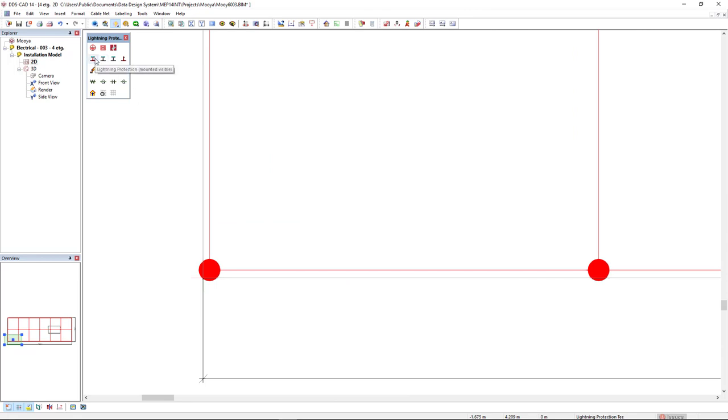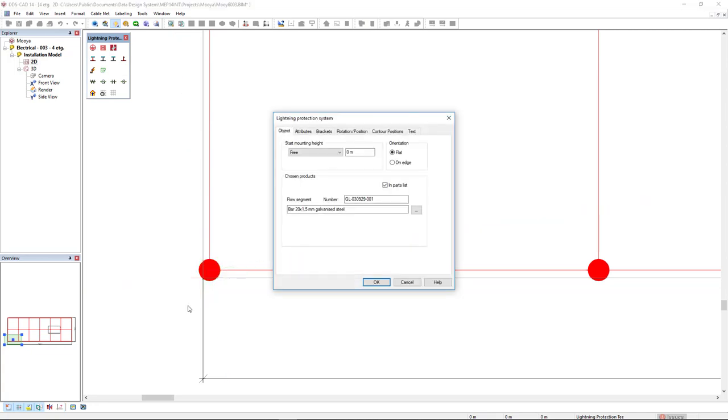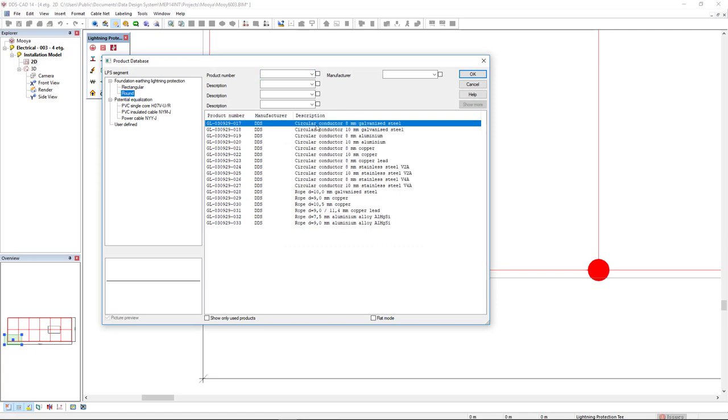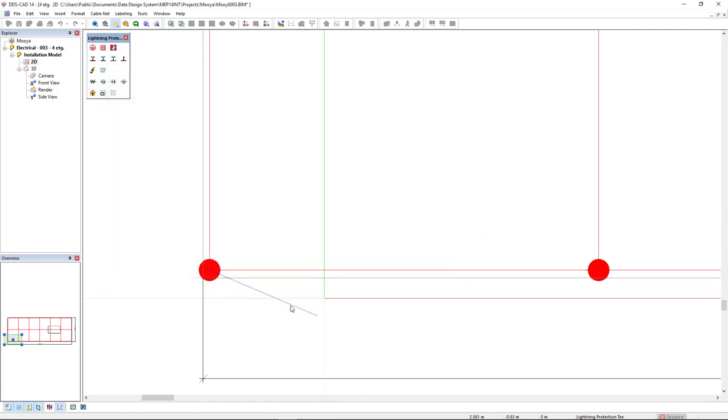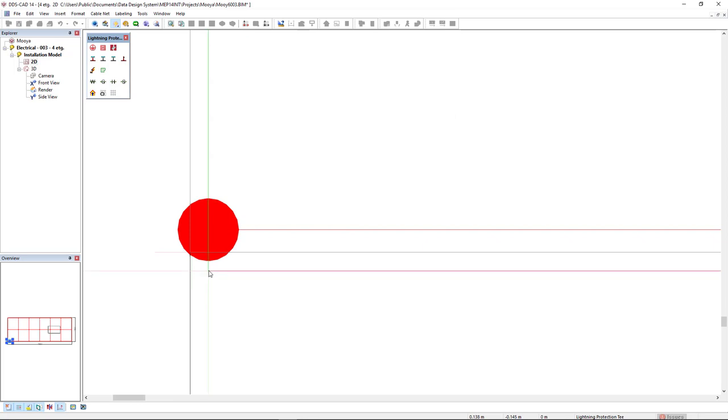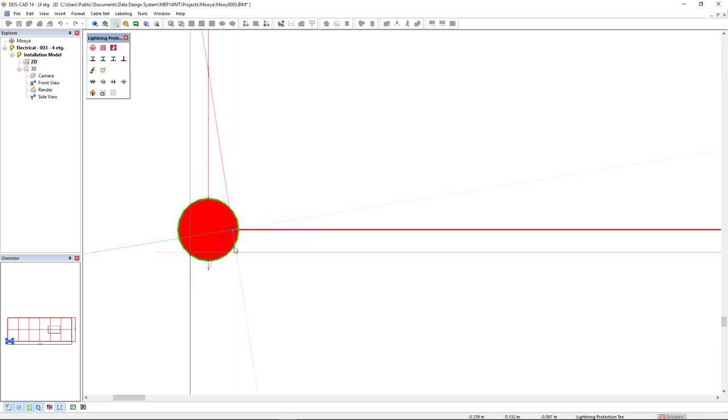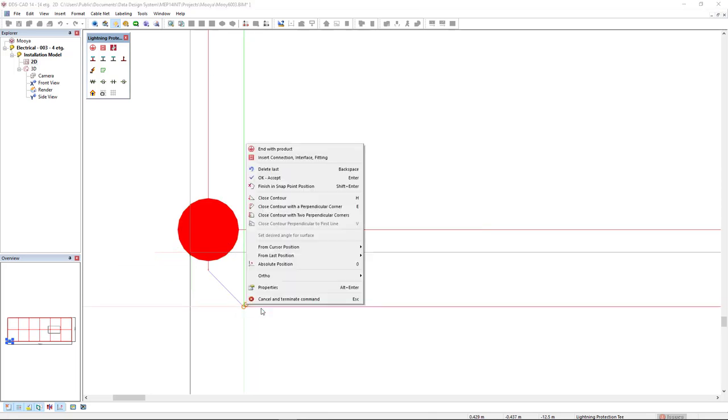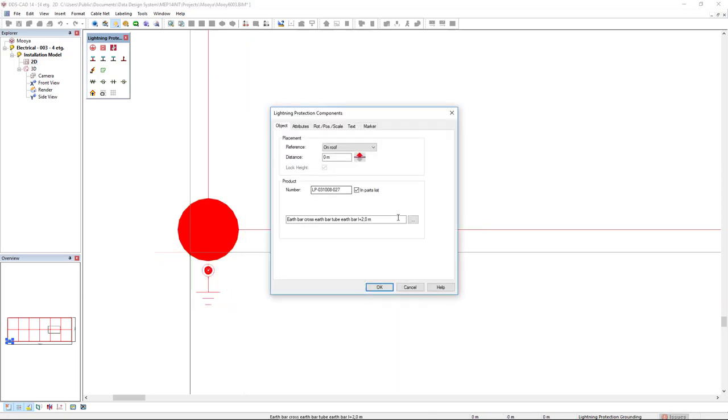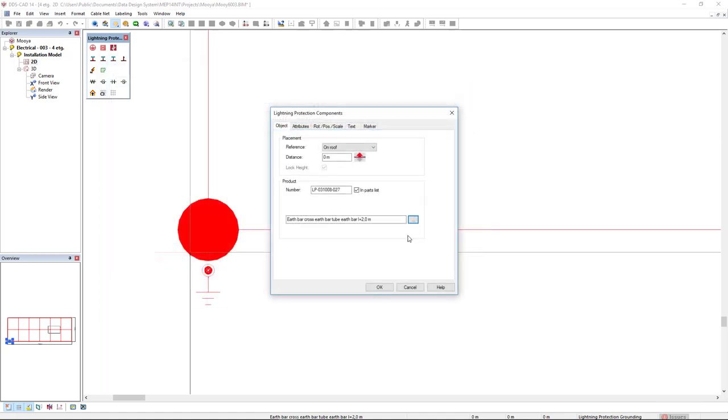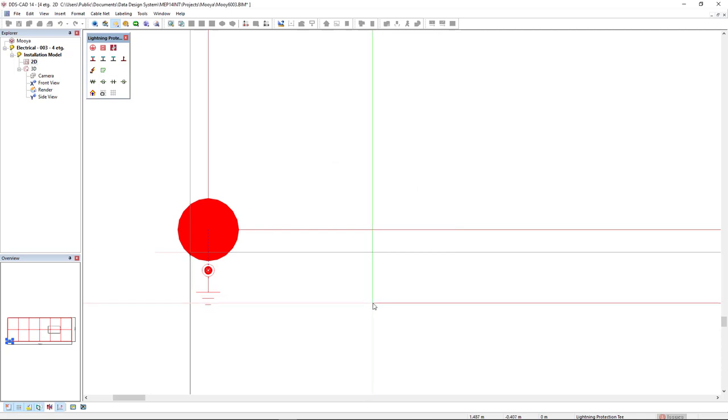Now I can come back to 2d and I will activate the lightning protection mounted visible and I will connect to this binding post and in the product database I will switch to a circular conductor. I move down and now I will press a hotkey page down and I will type minus 12.5 and then I will right mouse click and end with a product. In the product database I will select the category earth rods and I will select this earth bar cross earth bar tube earth. Okay.